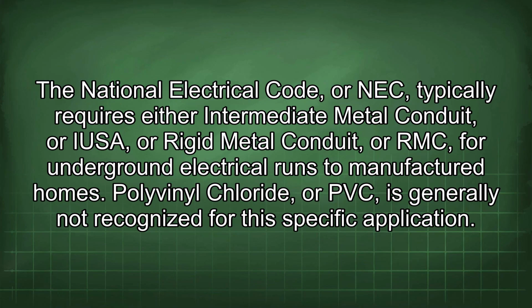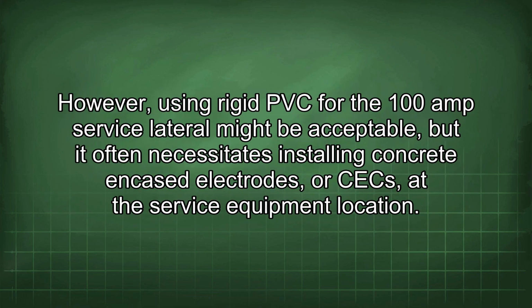The National Electrical Code, or NEC, typically requires either intermediate metal conduit, or IMC, or rigid metal conduit, or RMC, for underground electrical runs to manufactured homes. Polyvinyl chloride, or PVC, is generally not recognized for this specific application. However, using rigid PVC for the 100 amp service lateral might be acceptable, but it often necessitates installing concrete encased electrodes, or CEEs, at the service equipment location.